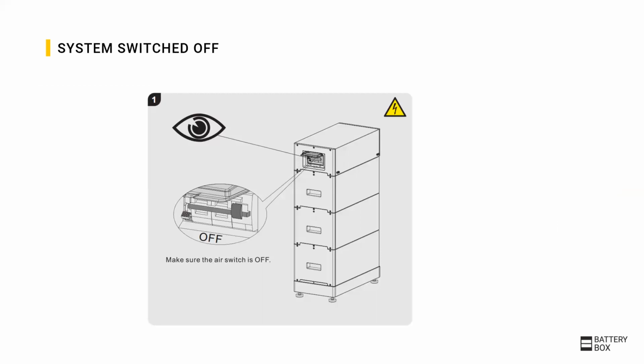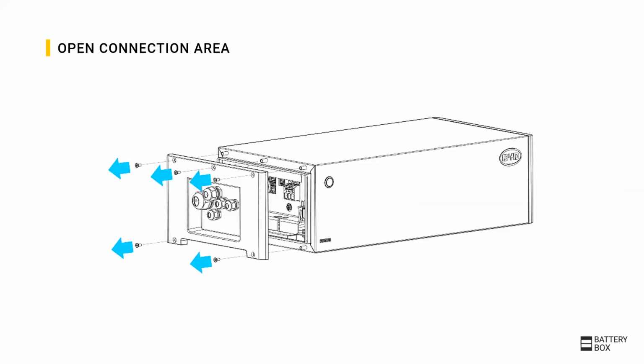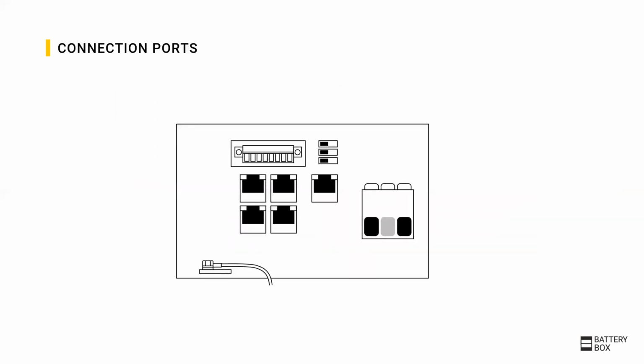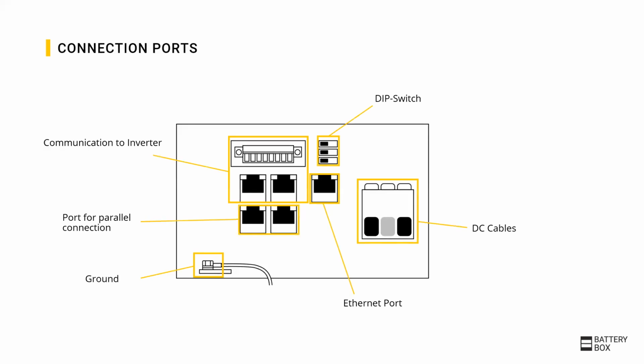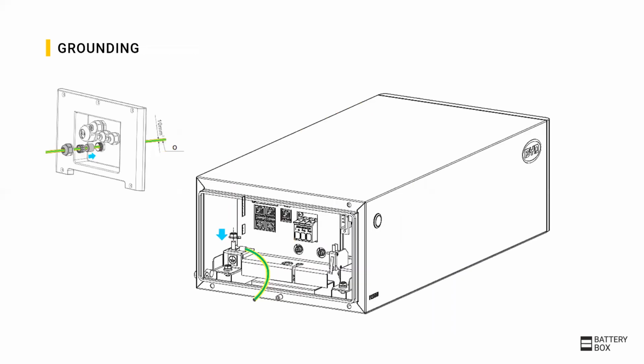Make sure the system switch is off before you start. Then open the connection area. Here you see the ports available in the connection area. You have the communication port to the inverter, the port for the parallel connection, the ground, the Ethernet port, the DC cables, and the dip switches.